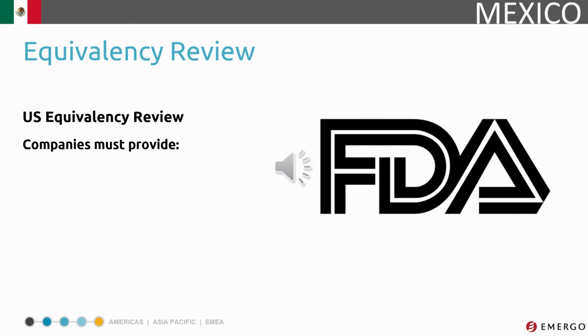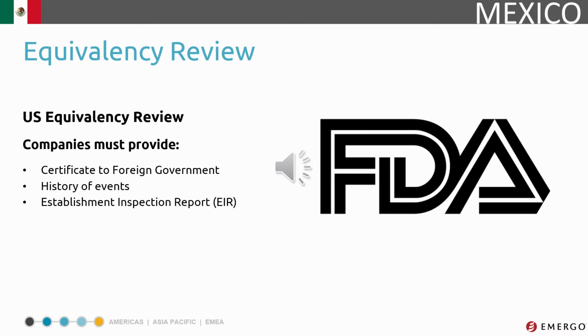Of the 3 equivalency markets, the US is the most difficult, especially if you lack any of the required documentation. Your registration application must include your certificate to foreign government and a history of all adverse events for the device. You are also required to include your establishment inspection report. This can prove to be difficult if the FDA either has not performed that inspection or neglected to give you the report. You can use this route for Class 1, 2, or 3 devices.